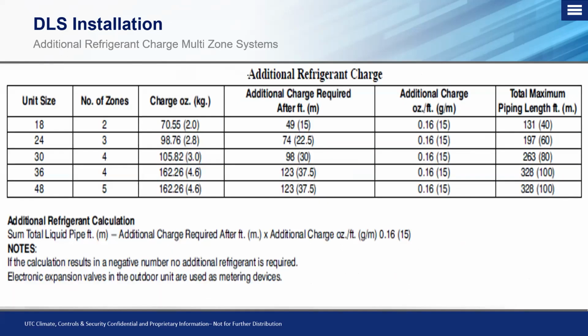Now, looking at the additional charge in the multi-zones, you'll see on here on your size 18,000, which is the smallest multi-zone that we have, 2 zones. And you'll see on here your additional charge required is 49 feet. Wait a minute, I thought you said it was 25 feet. Well, remember, you have 2 zones. You take that 49 divided by 2, you're at about 25 feet, and that's what that factory charge is good for.